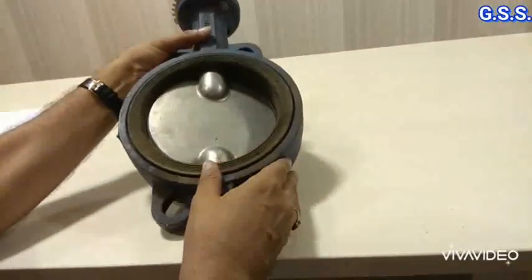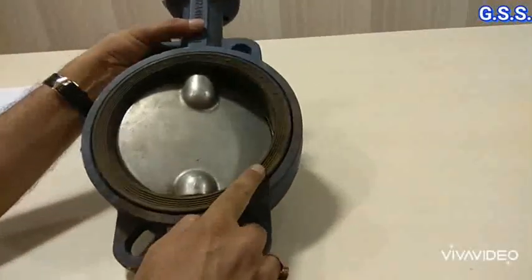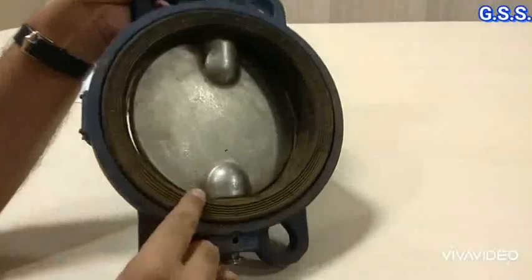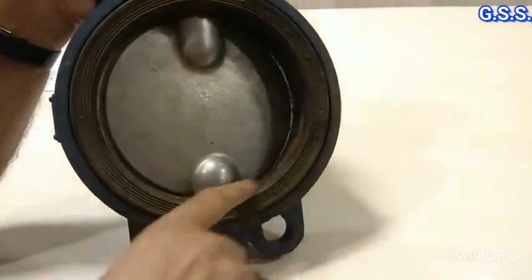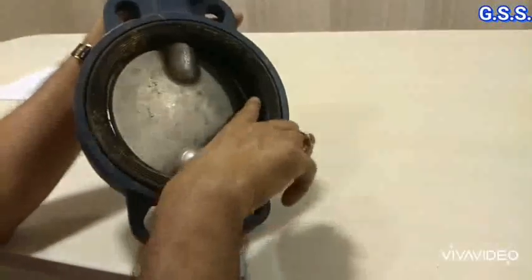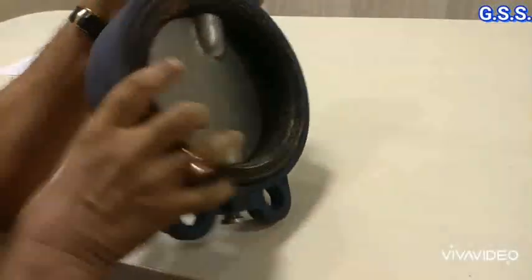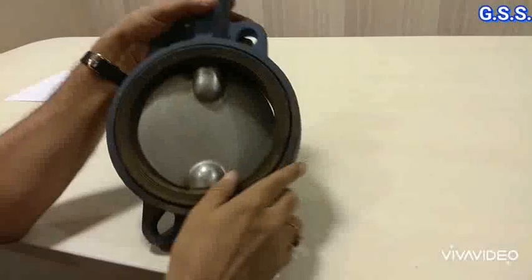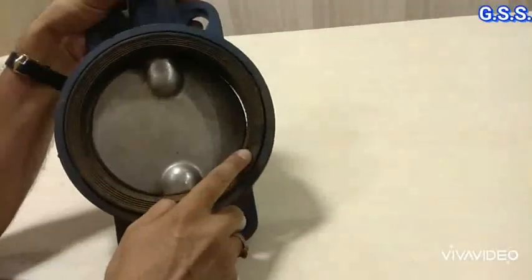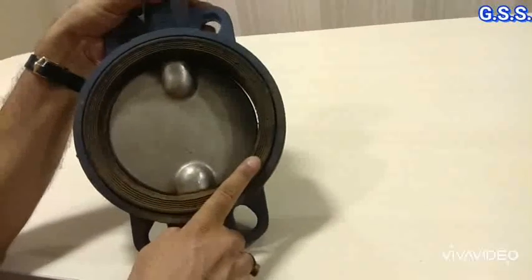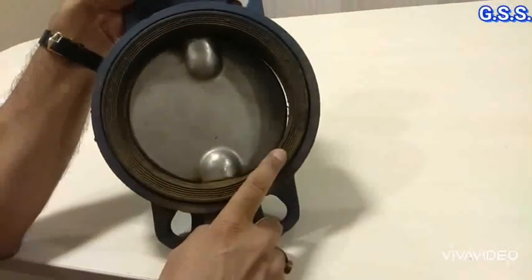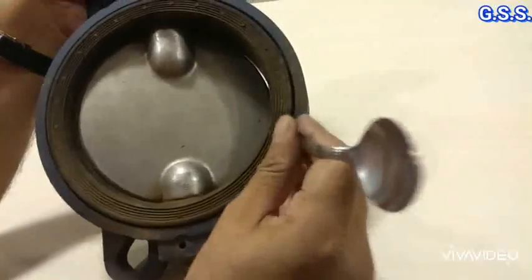Now this valve is having soft seat all around inside the body. This is the soft seat, inside the body is also soft seat and this side also inside the body is soft seat. Now this seat is of neoprene or EPDM means ethylene propylene diene monomer. This soft seat is replaceable.